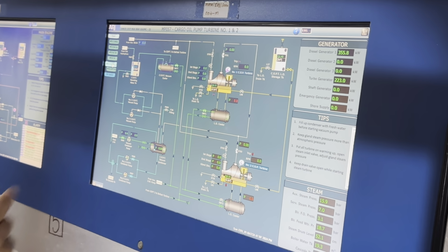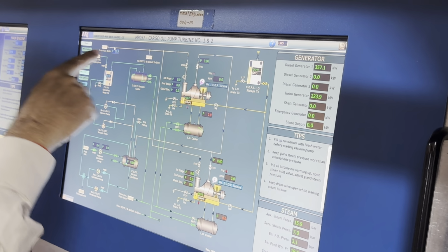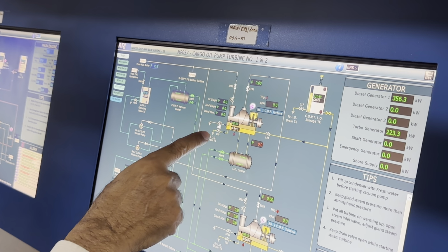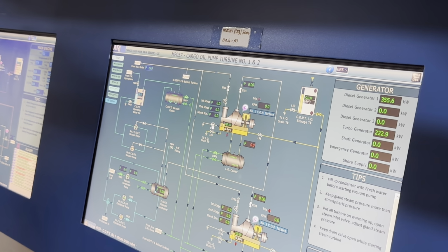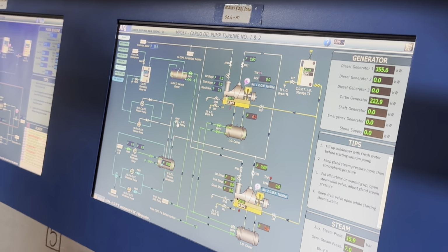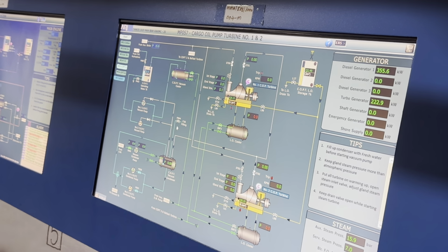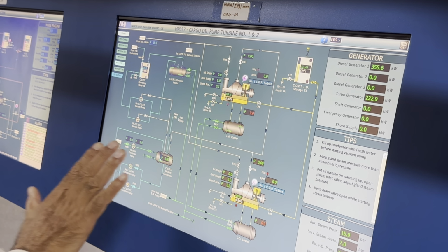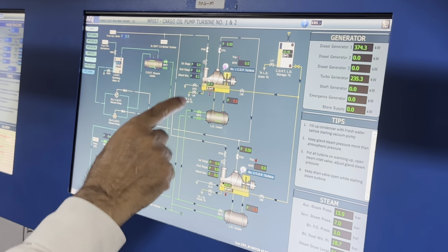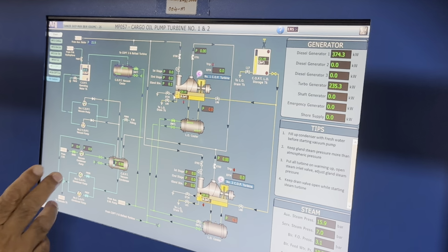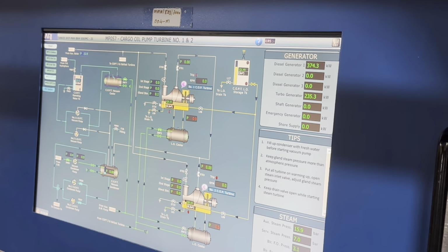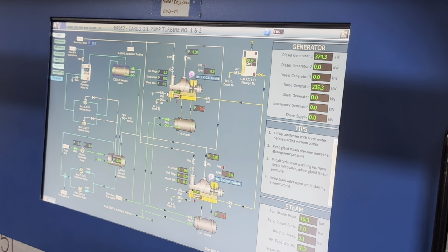So now this is the valve for steam coming from the auxiliary boiler. Open that, and open this drain valve for a while. Close, you must close. The steam is already closed. That is enough. See the gland steam pressure building up, and you have already drained. So now you see whether the vacuum is building up or not. Checking here. You wait and see.